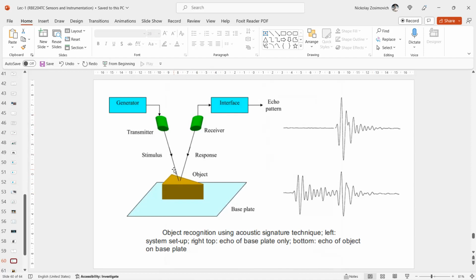The echo pattern from a test object belonging to the trained set is matched to each of the stored signals. Using a minimum distance criterion reveals the best candidate. Evidently, the test conditions should be the same as during the learning phase. A fixed geometry and a stable stimulus are required. The comparison process may be performed either in the frequency domain or in the time domain.